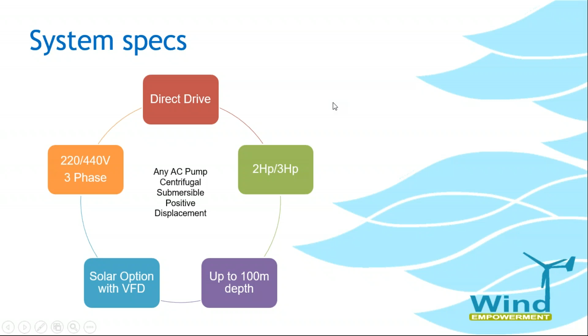And lastly, the last pump is obviously a positive displacement pump. One characteristic is that the positive displacement pump, which is the one used in Argentina, is actually better suited for variable speed, so you could have higher efficiencies from those pumps, but they tend to be a bit more expensive than a standard pump. Fortunately, Esteban will talk to you about the pumps they make in Argentina. At this point we have not tested our positive displacement pump, but we would love to. Next slide, please.